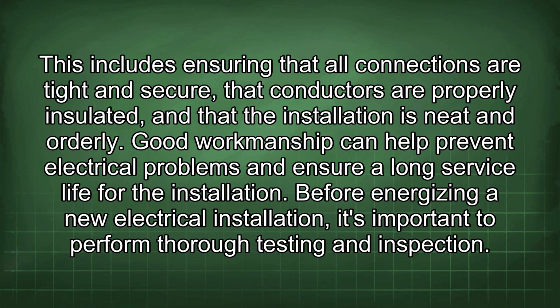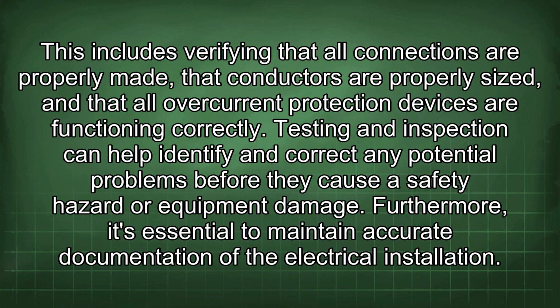Before energizing a new electrical installation, it's important to perform thorough testing and inspection. This includes verifying that all connections are properly made, that conductors are properly sized, and that all overcurrent protection devices are functioning correctly. Testing and inspection can help identify and correct any potential problems before they cause a safety hazard or equipment damage.